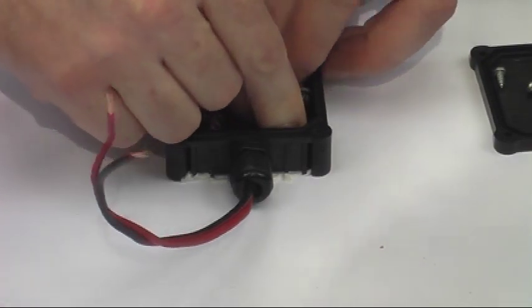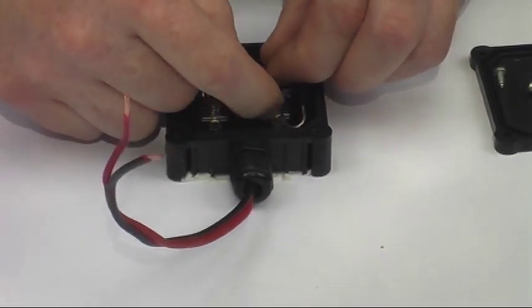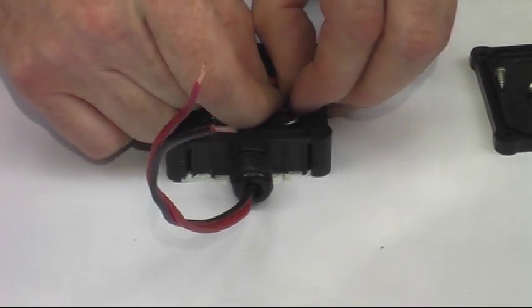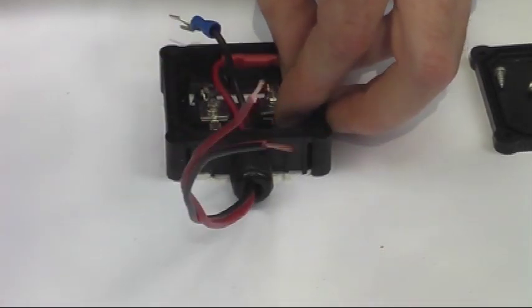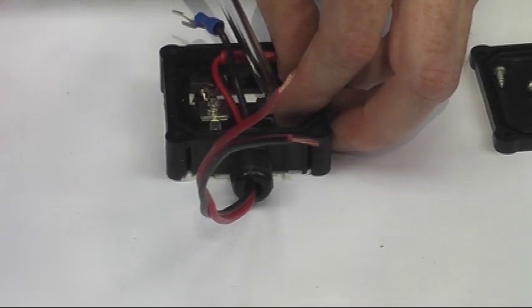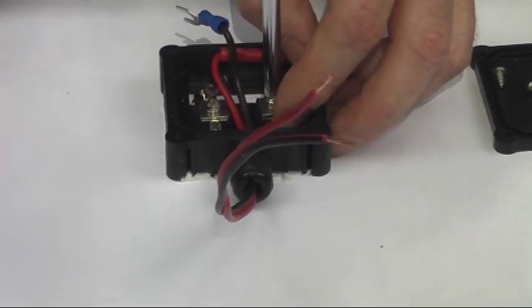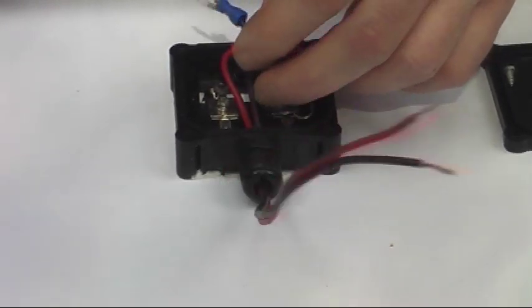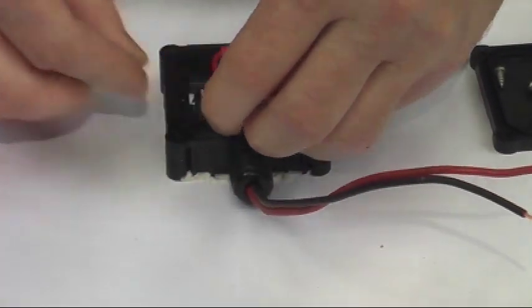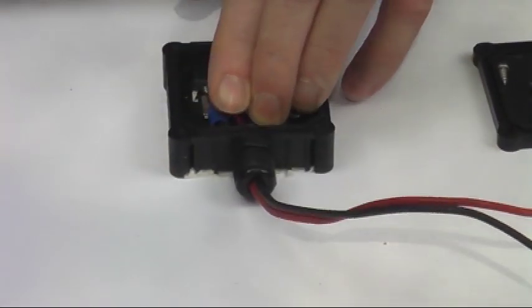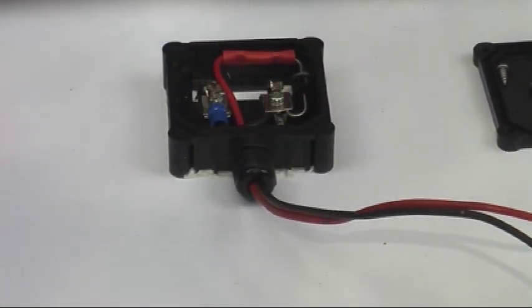That's how you fit the diode in. Then you screw everything down tightly, put the cover back on the box. Always remember the black wire goes to the negative terminal and the red wire goes to the positive terminal and it must have a blocking diode in it and the blocking diode must have the silver band facing the battery.